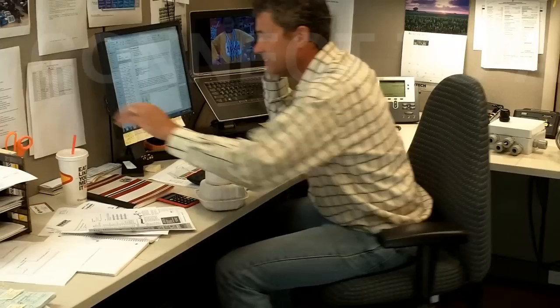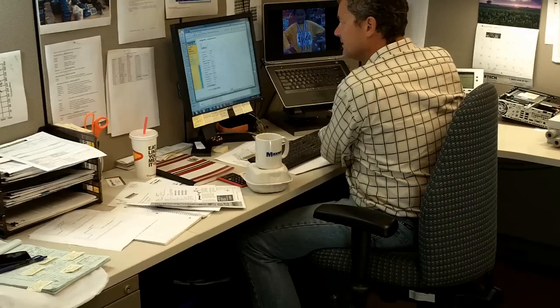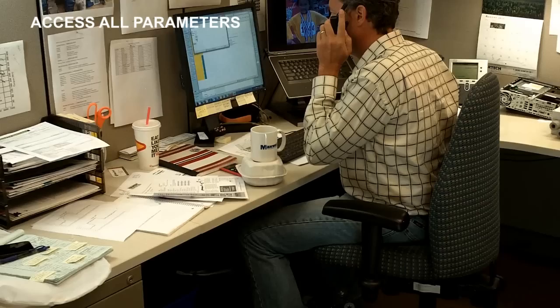Any web browser allows you complete remote access to your Ethernet-connected instrument. That's mixer number three. Just type in the IP address — it's got a 120-pound dispense set point. Access and adjust any of the configuration data. Hold on, I'm going to zero the thing out. Monitor, calibrate, tare — all commands are at your disposal.